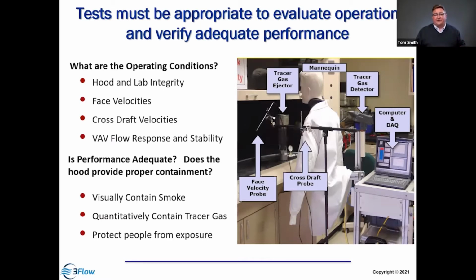So what's the face velocity? What's the cross drafts? What's the pressure? How well does it respond to opening and closing the sash? That's how well it's operating. But under that set of operating conditions, how well does it contain? We can visualize it with smoke. We can subject it to a tracer gas test. VAV response and stability is also another test that we want to run. So we're going to try and protect people. We can do the containment test visually, or we can do a more quantitative tracer gas test.